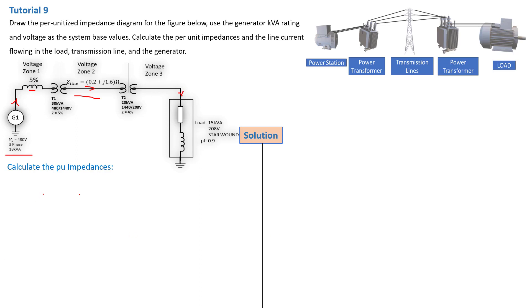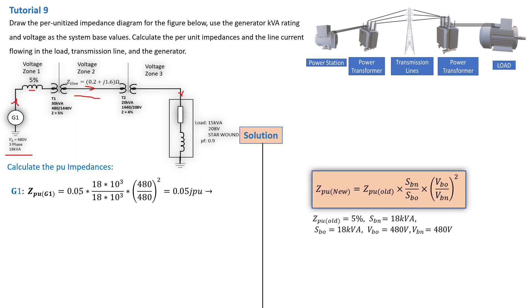For zone one, the voltage is 480 volts — that is the generator zone voltage. The new per unit value for the generator G1 is calculated as follows: Z per unit new equals Z per unit old, which is 5%, multiplied by (SB_new / SB_old) and (VB_old / VB_new)². Here SB_new is 18 kVA, SB_old is also 18 kVA because we are using the generator as the base, and both VB_old and VB_new are 480 V. Substituting into the formula gives us Z_G1 = 0.05 per unit.